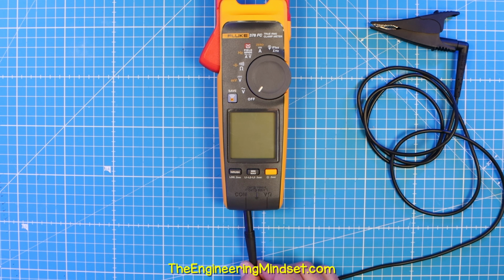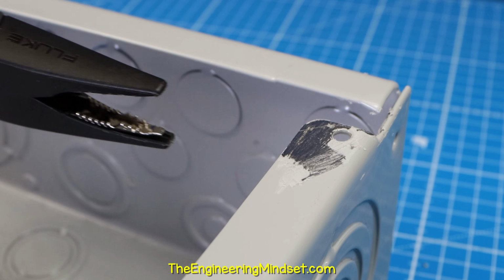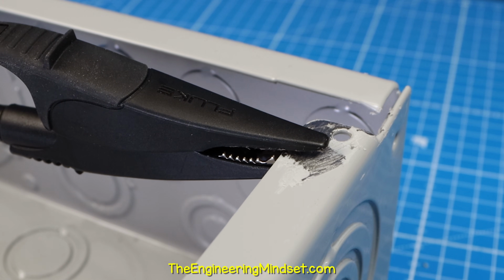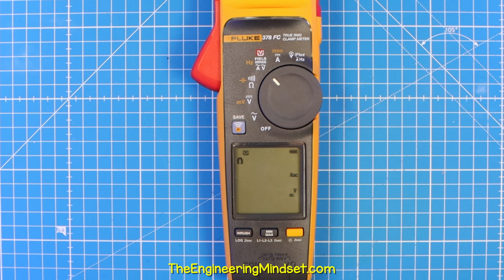Or we can use this clamp. We just connect our ground wire and clamp it to a grounded surface to provide a reference, and then we select the AC voltage field sense function.